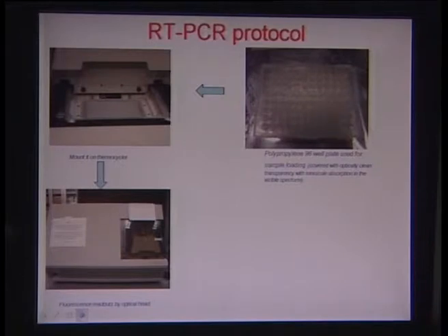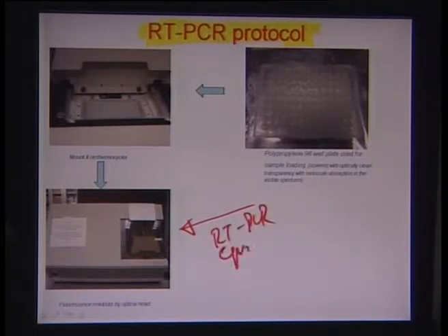Normally we do need to read out the fluorescence signal very quickly, and for that, especially in the RT-PCR or qPCR reactions, we do have a separate reader unit. So essentially there are two aspects here. One is there has to be a reader head. You can see this is essentially an equipment from Stratagene. This is the RT-PCR equipment, and this right here is also the fluorescence readout mechanism.